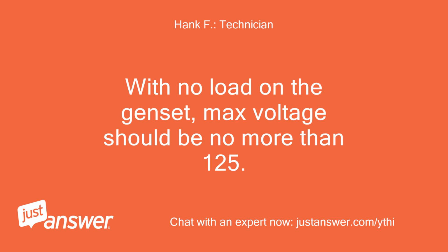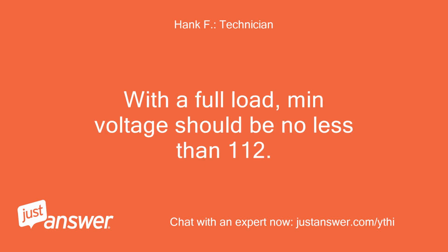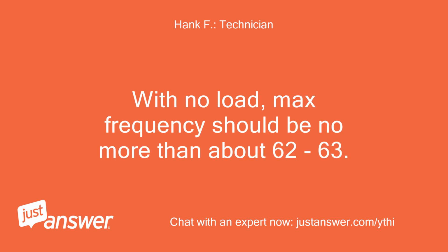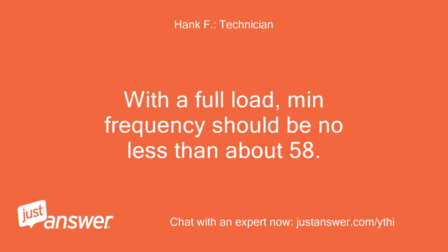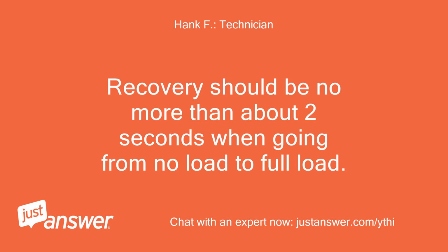With no load on the genset, max voltage should be no more than 125. With a full load, min voltage should be no less than 112. With no load, max frequency should be no more than about 62 to 63. With a full load, min frequency should be no less than about 58. Recovery should be no more than about 2 seconds when going from no load to full load.